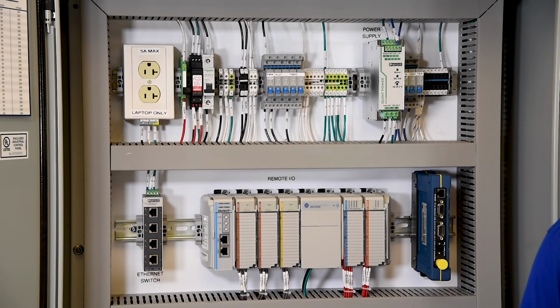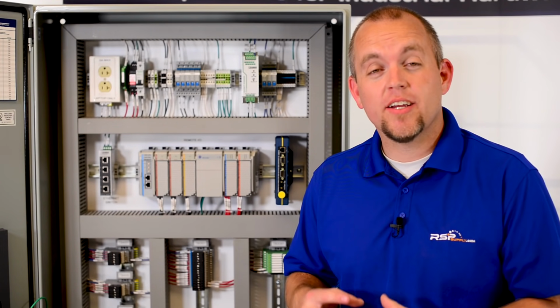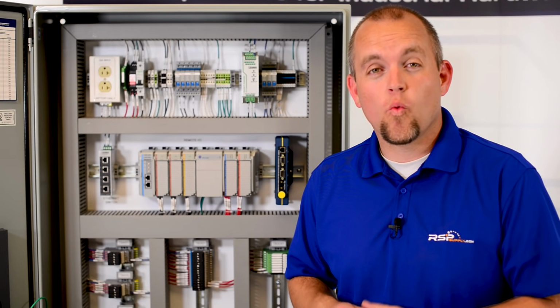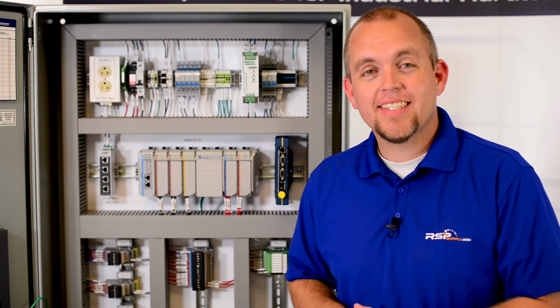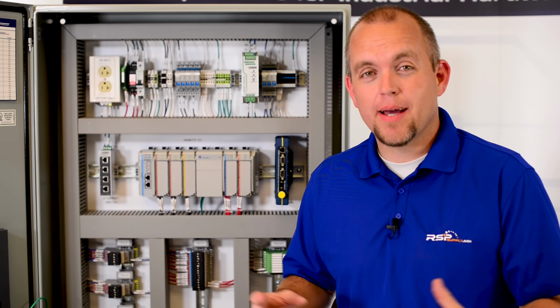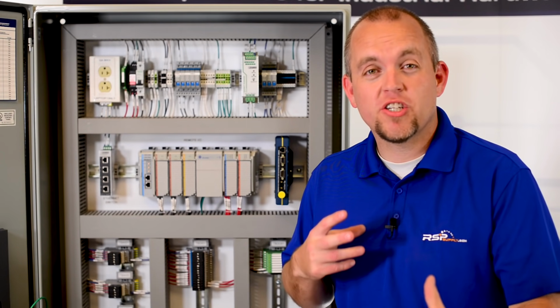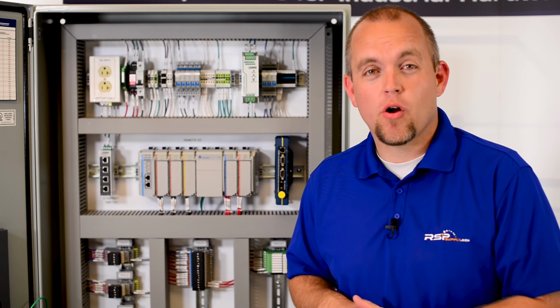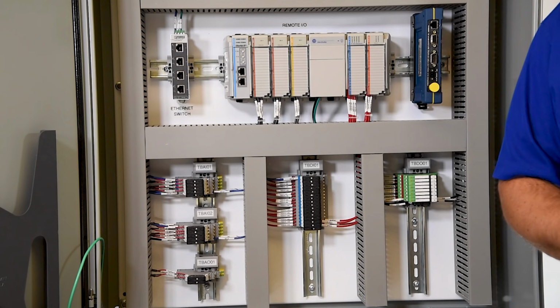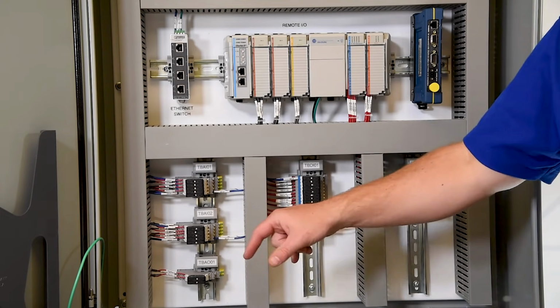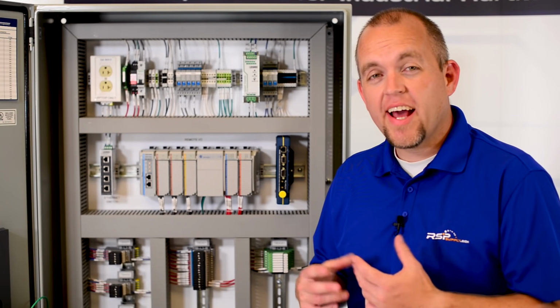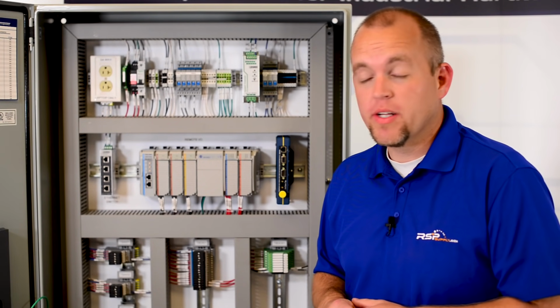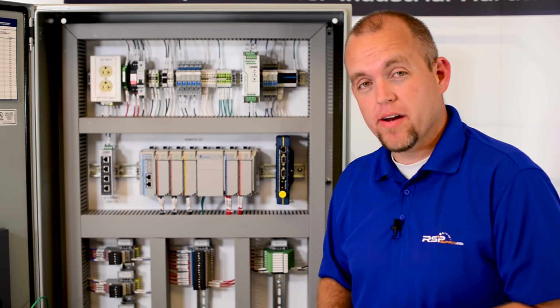Now let's talk about the brains of the operation, the PLC, or Programmable Logic Controller. The purpose of the PLC is to send and receive data to the instruments that are wired in the field. It takes that data with varying signal types, translates it so that we can understand it and incorporate that into our distributed control systems. Now let's talk about the terminal blocks. The terminal blocks are the connection point where field instruments are wired into our control panel.